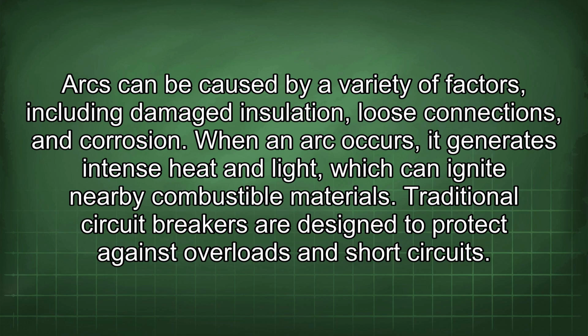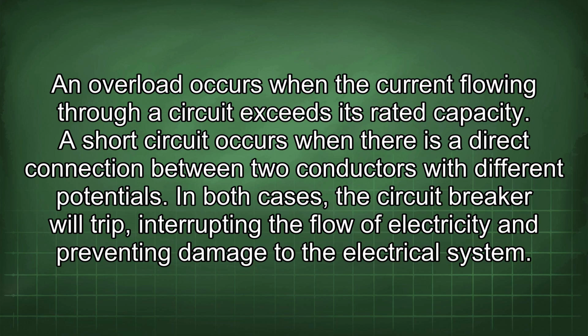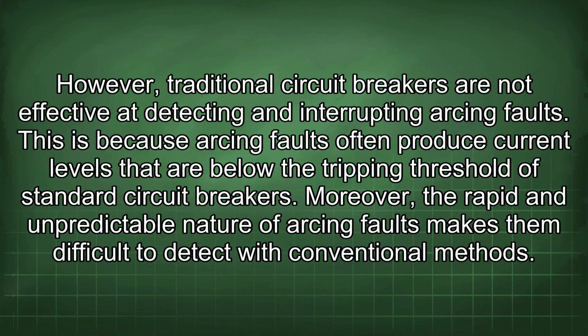Traditional circuit breakers are designed to protect against overloads and short circuits. An overload occurs when the current flowing through a circuit exceeds its rated capacity. A short circuit occurs when there is a direct connection between two conductors with different potentials. In both cases, the circuit breaker will trip, interrupting the flow of electricity and preventing damage to the electrical system. However, traditional circuit breakers are not effective at detecting and interrupting arcing faults. This is because arcing faults often produce current levels that are below the tripping threshold of standard circuit breakers. Moreover, the rapid and unpredictable nature of arcing faults makes them difficult to detect with conventional methods.